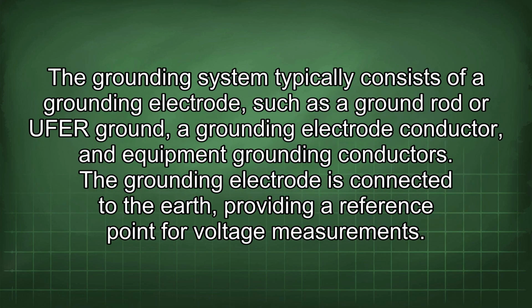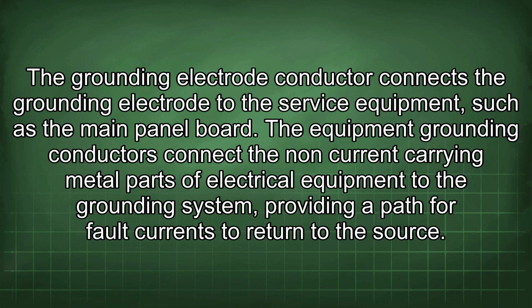The grounding system typically consists of a grounding electrode, such as a ground rod or UFER ground, a grounding electrode conductor, and equipment grounding conductors. The grounding electrode is connected to the earth, providing a reference point for voltage measurements. The grounding electrode conductor connects the grounding electrode to the service equipment, such as the main panel board. The equipment grounding conductors connect the non-current carrying metal parts of electrical equipment to the grounding system, providing a path for fault currents to return to the source.